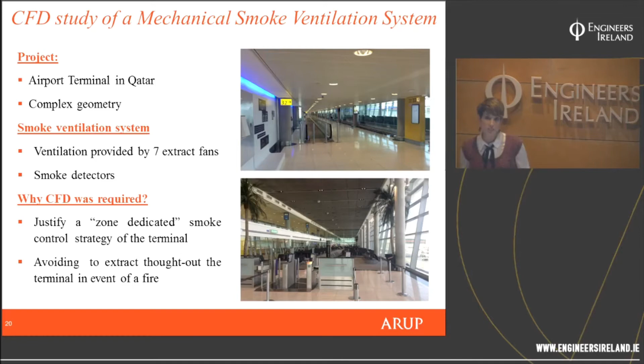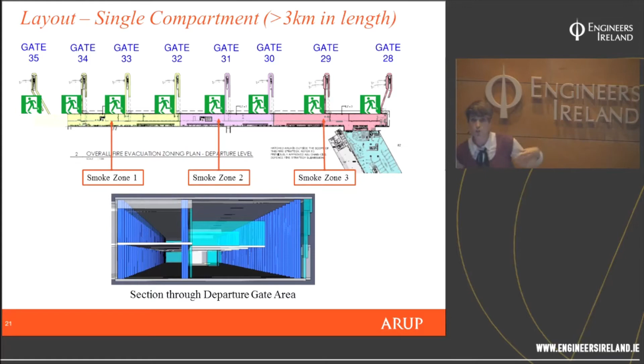CFD in this case was used to justify an open plan area with fewer evacuation routes, and also an optimized use of the ventilation system. So instead of having 3 different compartments, we had 3 different smoke control zones, with the mechanical system operating on each control zone depending on where the fire was located. So without any physical separation, we virtually separated the ventilation system.